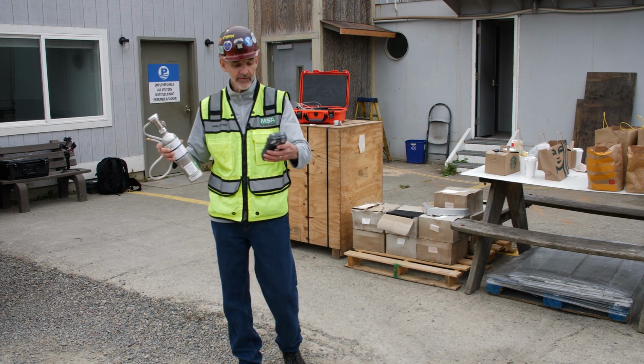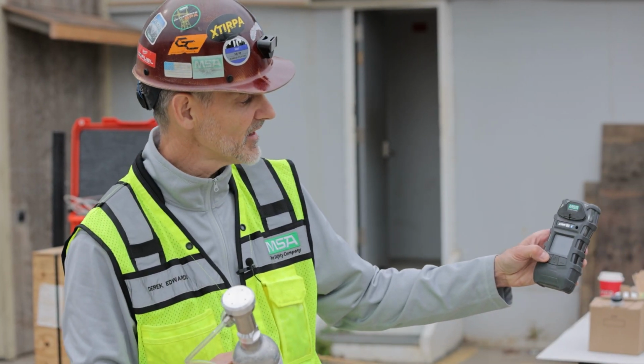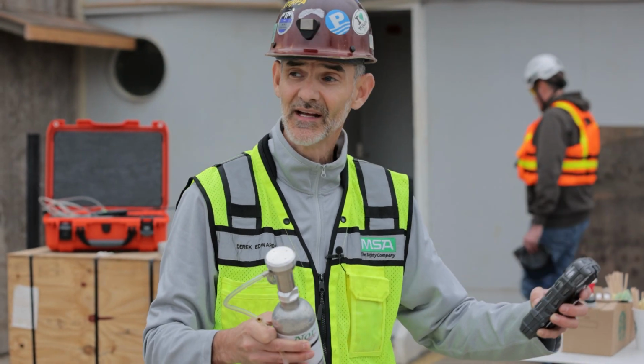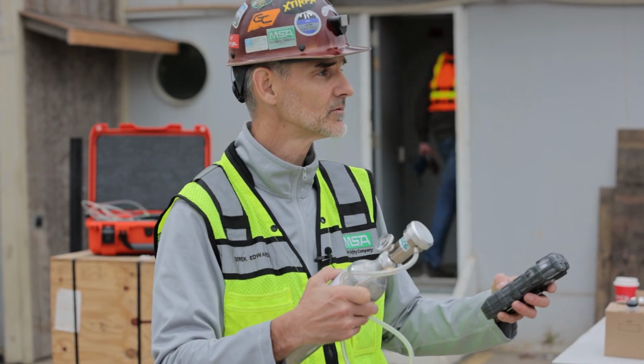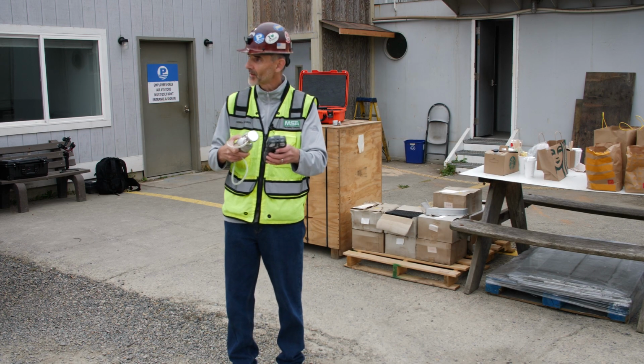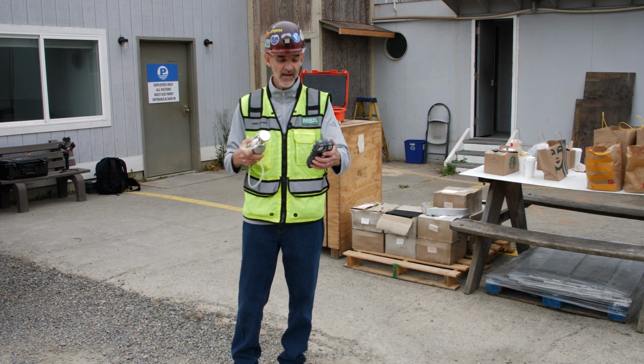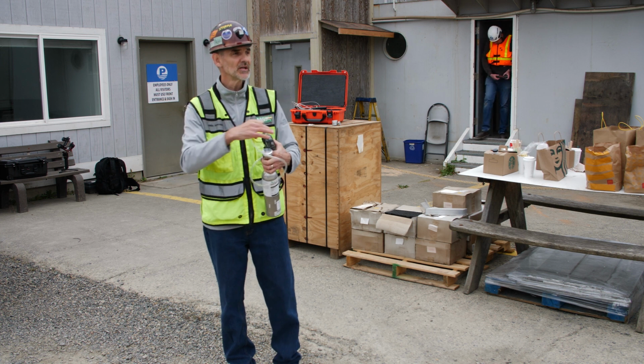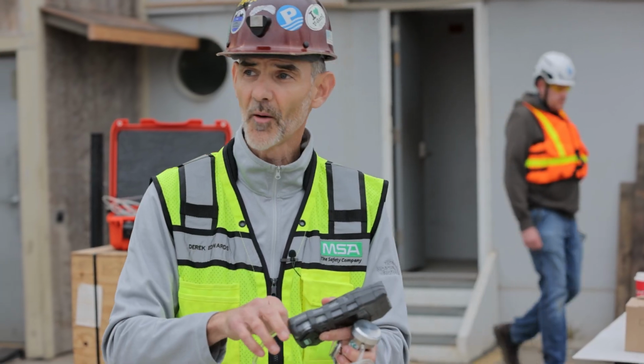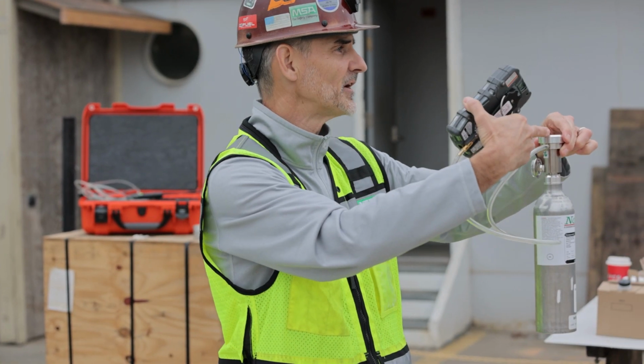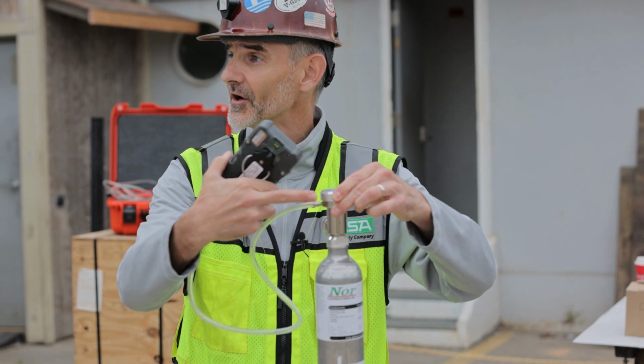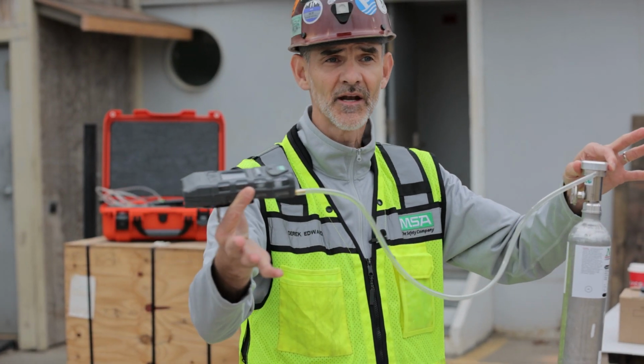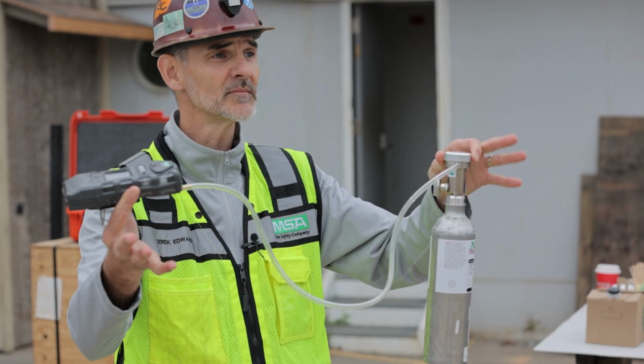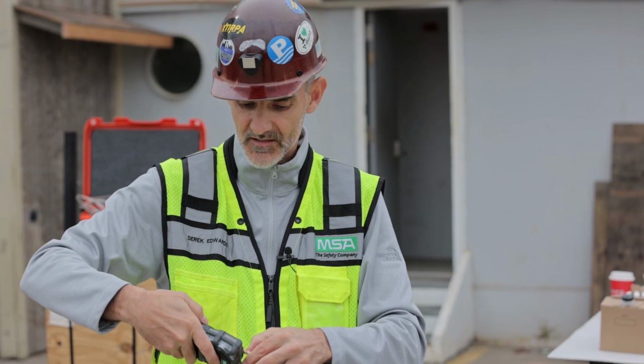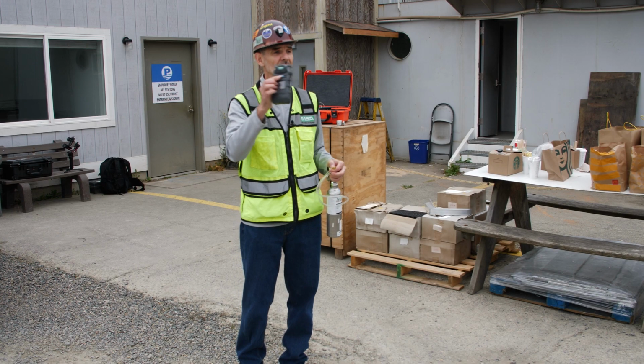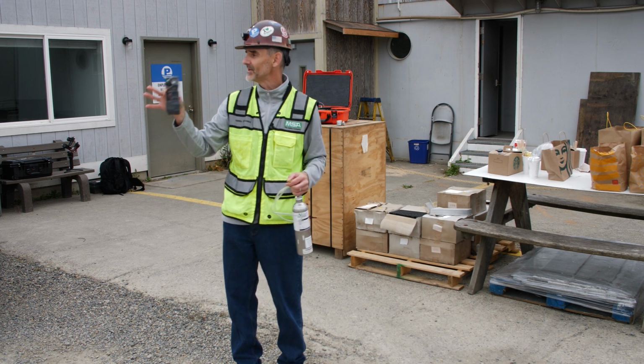So again, we look at the screen. It says bump on the left side. We press that button and it asks us a question. It says bump test, question mark, yes or no. We are going to say yes, which is the middle button. We press that. And now it says bump test and it's flashing. You don't need to push any more buttons. We simply apply the gas. This regulator does not have a knob on it. You can't turn it on. It's called the demand flow regulator. Gas is now flowing to our instrument. And in about 10 seconds, it's going to beep 3 times. You can't see it, but there are 4 check marks on here and our bump test pass. Now we know this instrument is reading correctly and ready to be used.